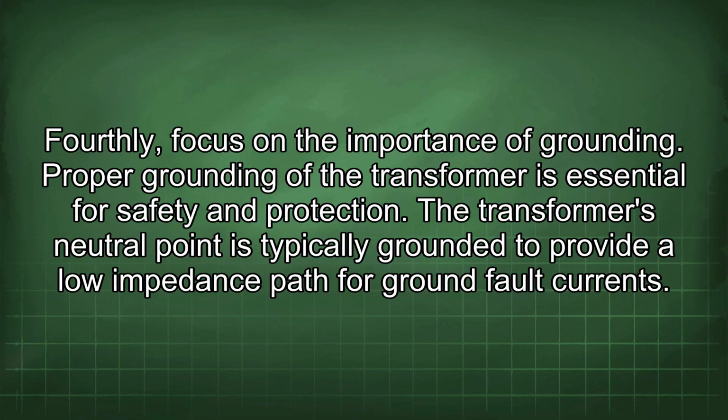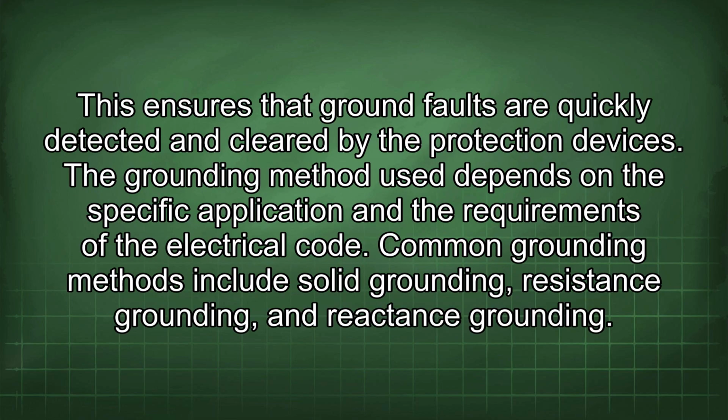Fourthly, focus on the importance of grounding. Proper grounding of the transformer is essential for safety and protection. The transformer's neutral point is typically grounded to provide a low impedance path for ground fault current. This ensures that ground faults are quickly detected and cleared by the protection devices.